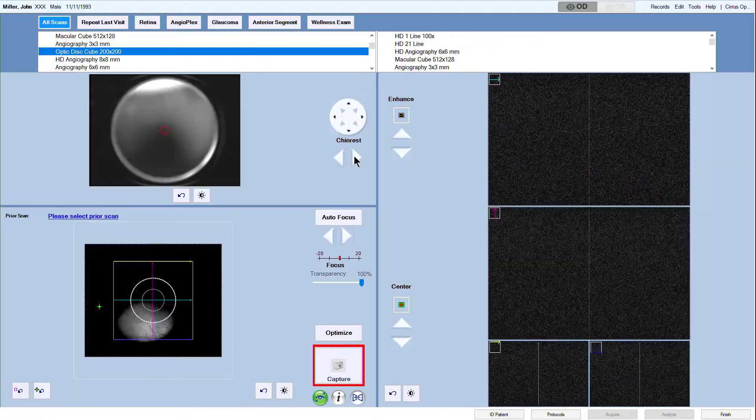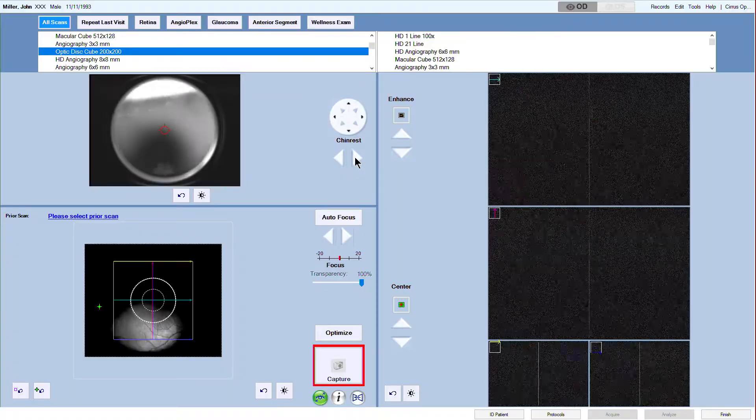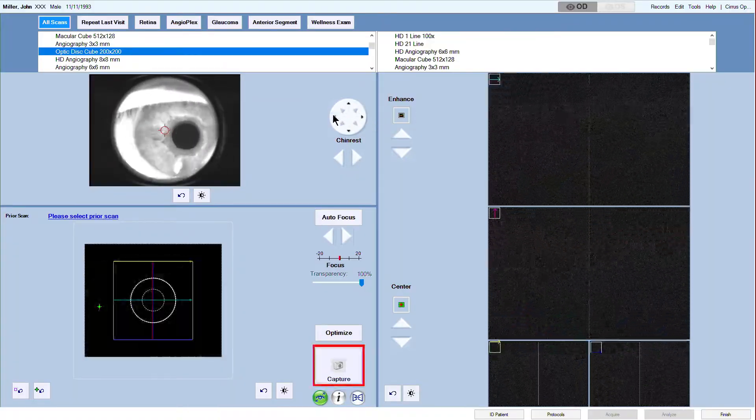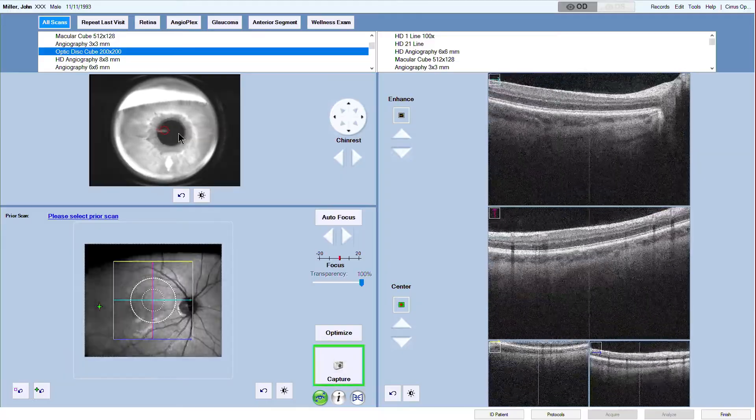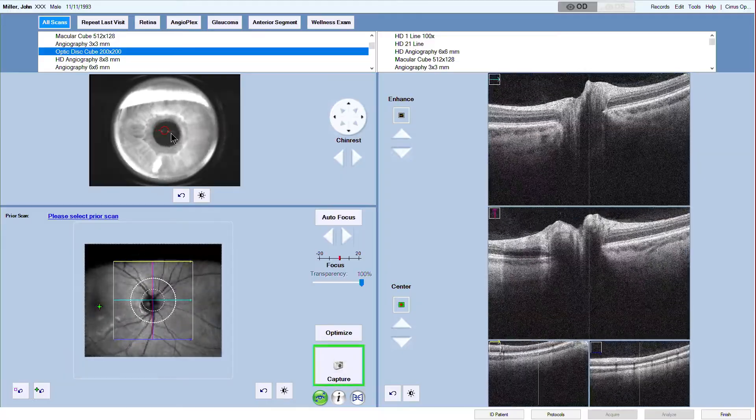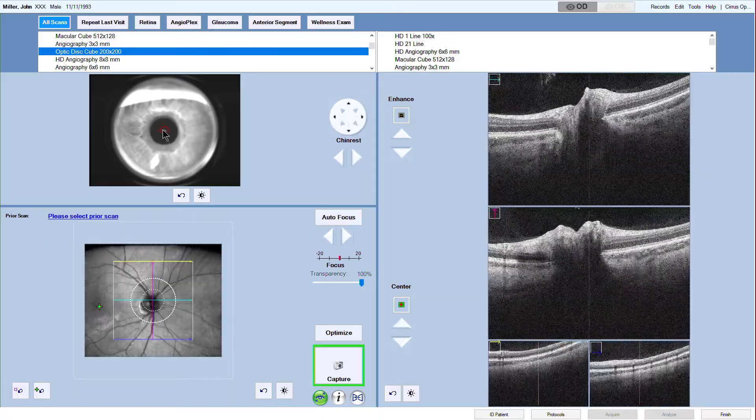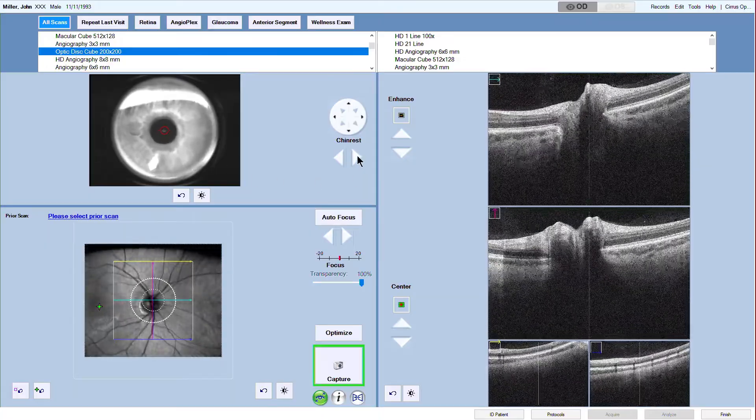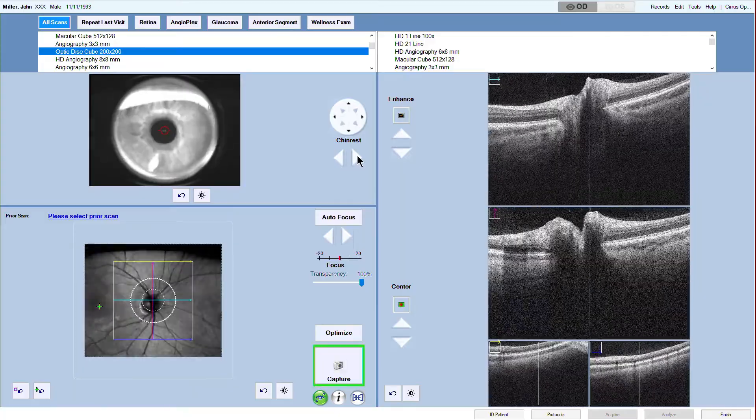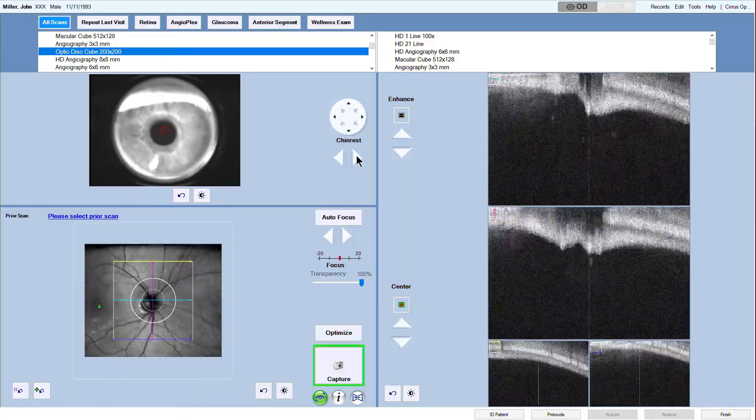Now start the alignment in the iris viewport. Center and focus the iris image using the controls to the right of the iris viewport. Center the iris image within the iris crosshairs by clicking on the center of the pupil. The chin rest will automatically move to the center of the eye. Try to get the iris as clear as possible before proceeding to the next step.